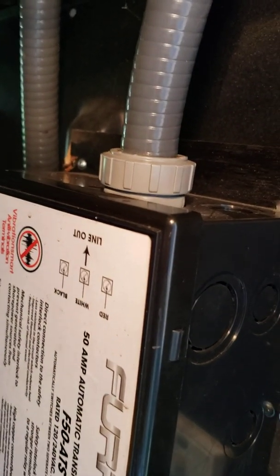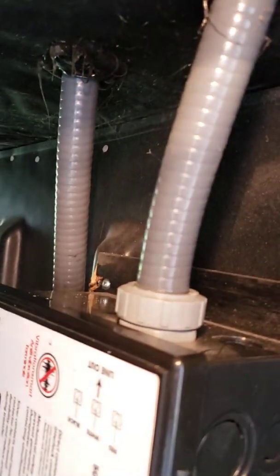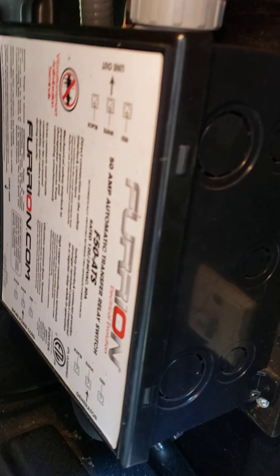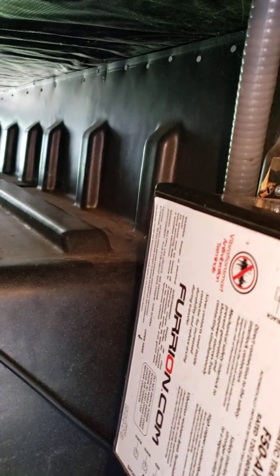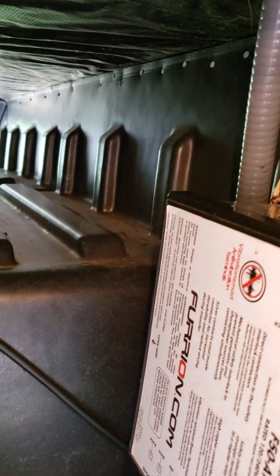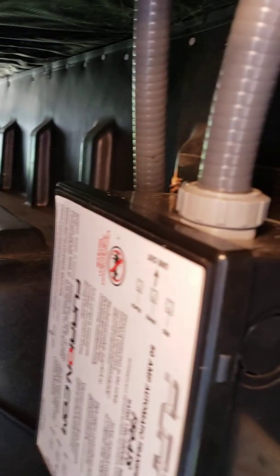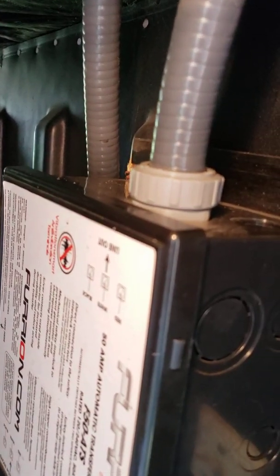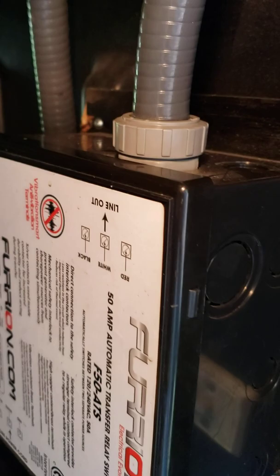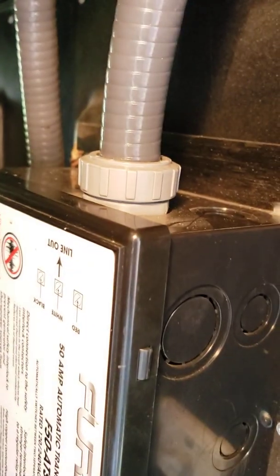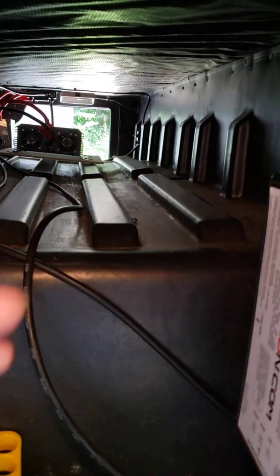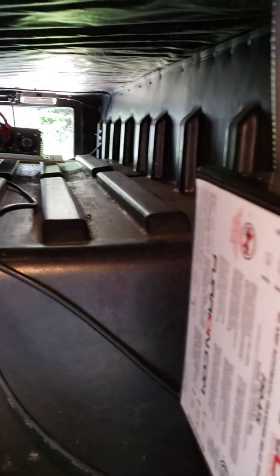I need to get the power from that inverter into the coach, but I don't want to disconnect this. So the solution was to add a second transfer switch right here. It's going to live right over there, and I'm going to show you how I'm wiring that in. This outlay, that's where all the tie-in is going to happen. This is all going to stay like it is. I'm going to use this line here to connect the other two together, and then that will be wired into the new transfer switch, and then all the power from that transfer switch will go out into the coach. So hang tight, and I'll kind of explain it a little better.